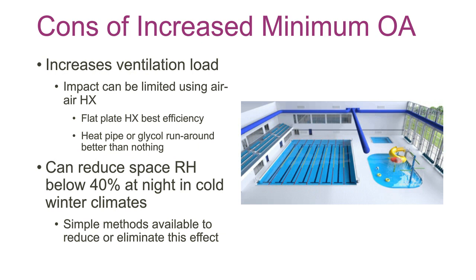Even at 25% outside air, you could reduce the space humidity below 40% at night in cold climates, and that's not desirable. Your evaporation is going up, and your pool water heating then is going up. But you can do some relatively simple things in an unoccupied mode to reduce or eliminate that and keep that in the 40 to 60% range that is recommended in the applications guide, because your evaporation is going down, you have a still pool, your chloramine production is going down, and you can justify reducing your outside air to some extent.